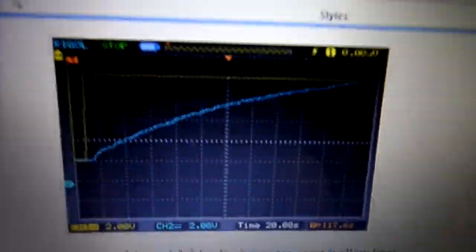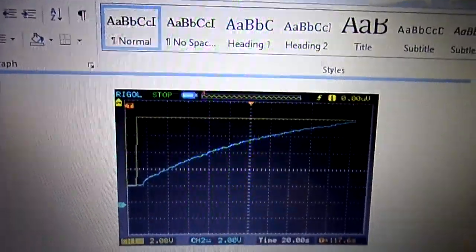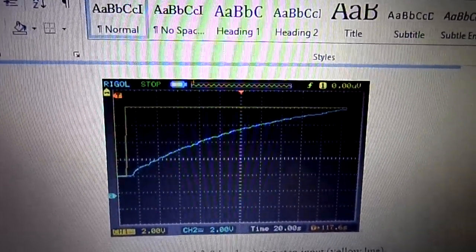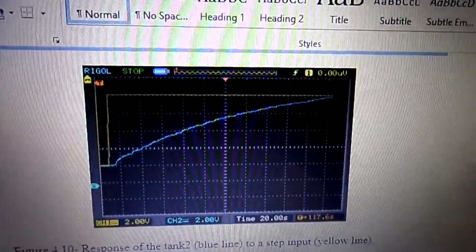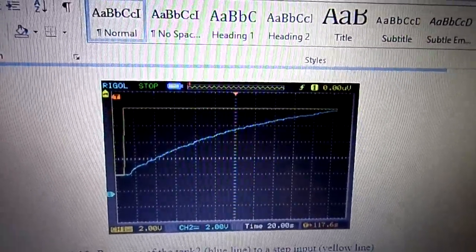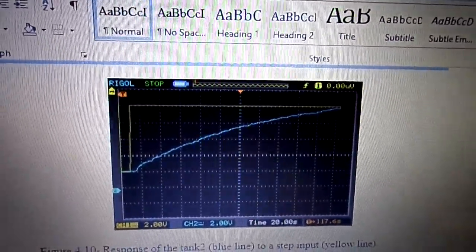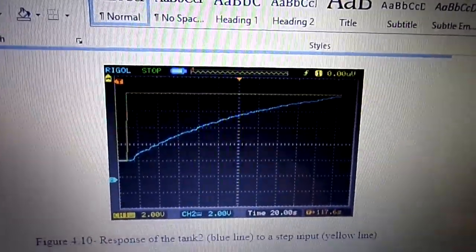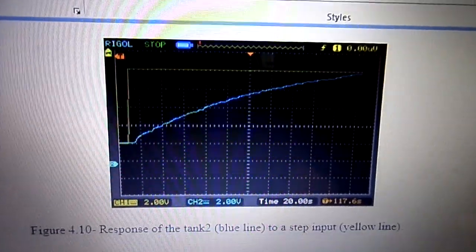This is a time response for physically measuring the plant. This was measured using the oscilloscope. I used the oscilloscope input from the set point to the plant, routed from PLC to oscilloscope channel one, and output coming from the level transmitter to channel two. That's what I got.